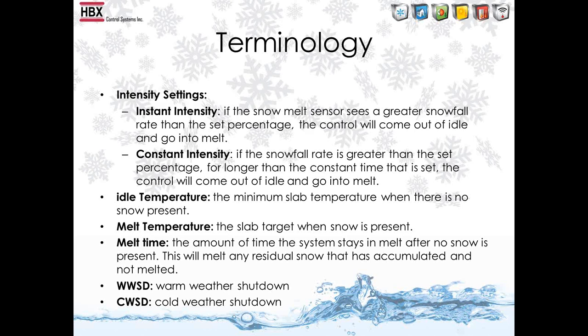Constant intensity: if the snowfall rate is greater than the set percentage for longer than the constant time set in the control, it will come out of idle and go into melt. Your idle temperature is a minimum slab temperature when there is no snow present. Your melt temperature is the slab target when snow is present. Melt time is the amount of time that the system will stay in melt after no snow is present — this will melt any snow that has accumulated and not yet melted.